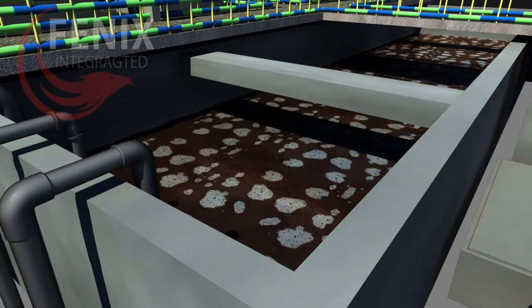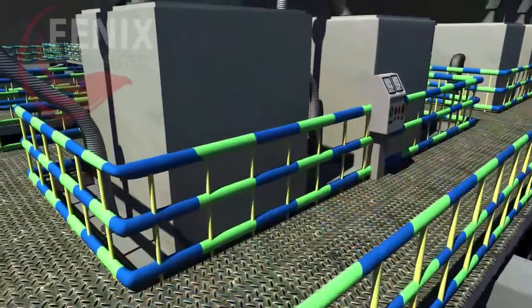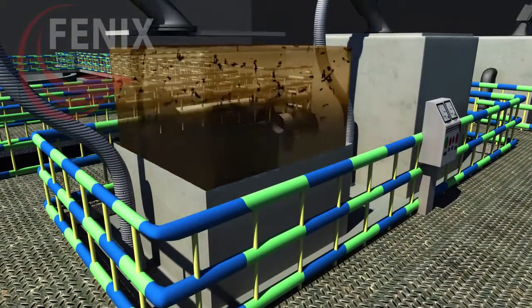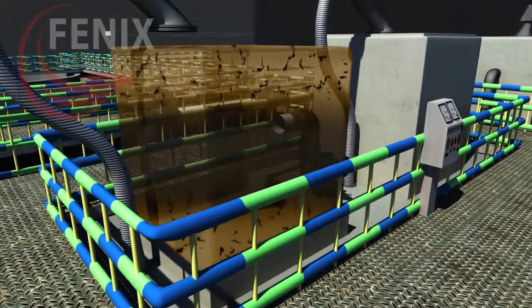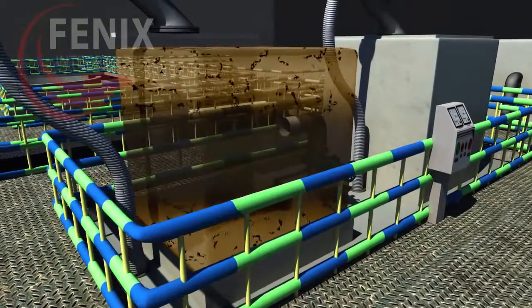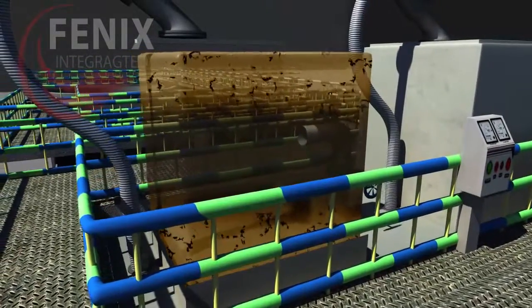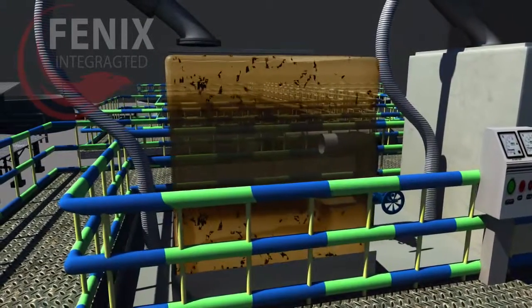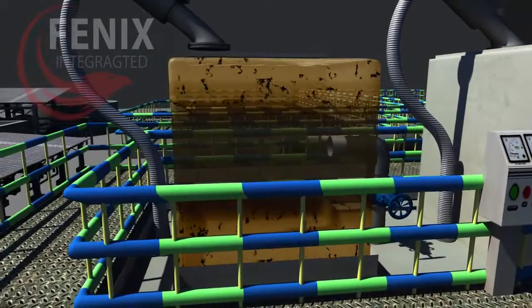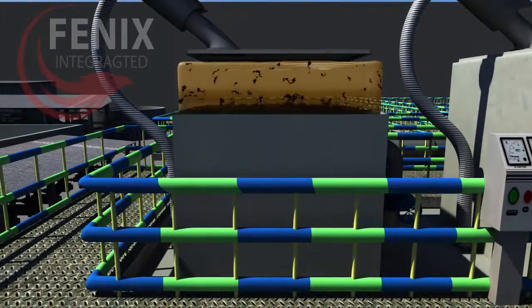Once the aeration and mixing is completed, the wastewater goes into the grit and grease removal tank. Grit are small stones and sand, so at this stage they go and settle at the bottom of the tank, out of which they will go into a bin. The grease and oil, on the other hand, are collected together on the surface by means of an air blower and then sucked outside the tank by a special pump provided for this task. Big particles carried by the wastewater will also settle at the bottom of this tank.